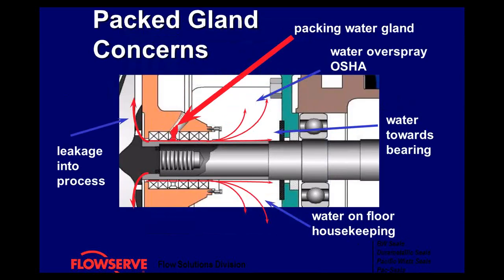Some of the problems: leakage into your process can cause contamination, especially if you don't want water in your system. Also, if you have overspray or water on the floor, this can be an OSHA concern and a housekeeping concern. Lastly, if water gets towards the bearings, it can contaminate the oil and eventually lead to a bearing failure.